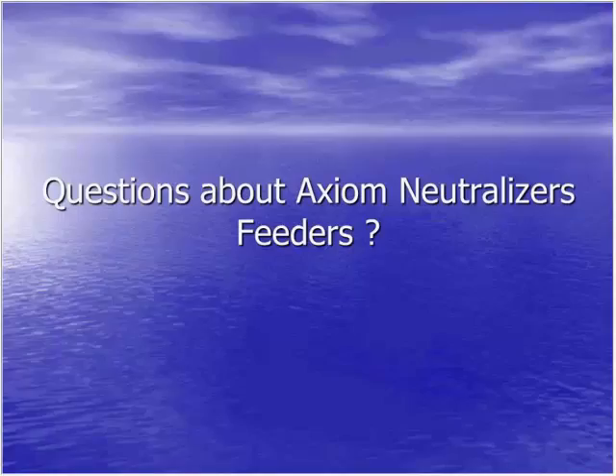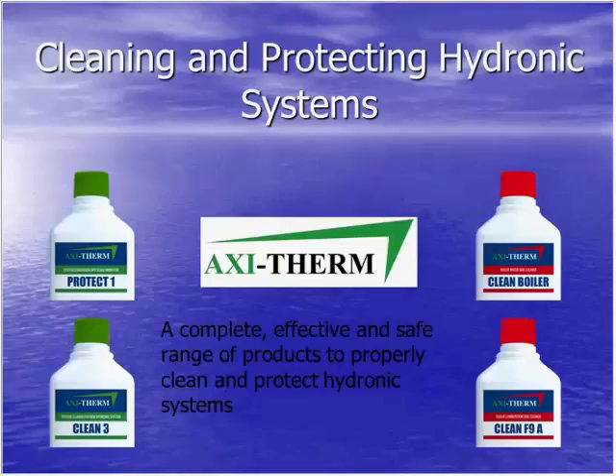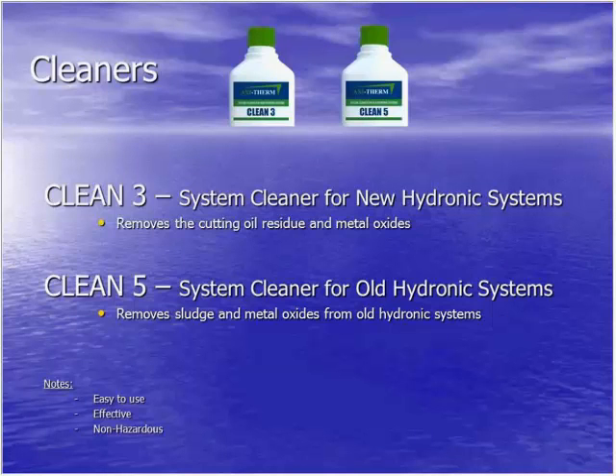Recently, Axiom unveiled a complete line of products to properly clean and protect hydronic closed loop systems. It's important to use a cleaner that's for the purpose you're cleaning it for. We've got two types of cleaners for closed loop systems. One's designed for new hydronic systems. Typically what you're going to see in there is cutting oil, flux, and some metal oxides, so you're going to have one that caters to cleaning those out when you clean and flush new systems.